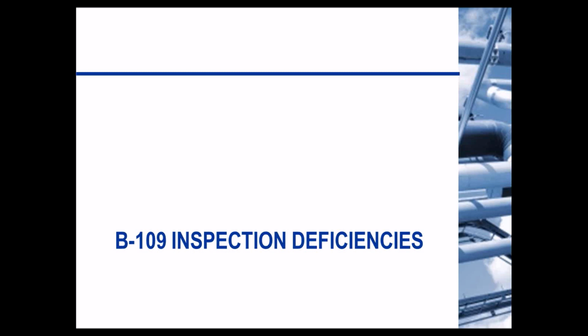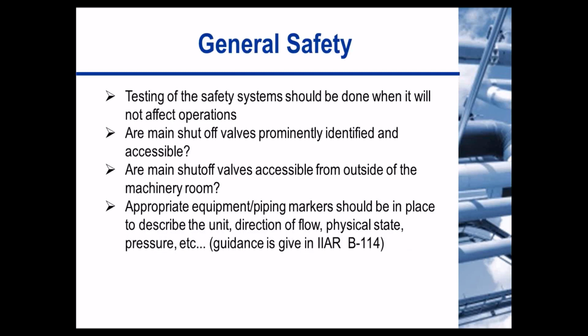So let's talk a little bit about the different inspection checklists and some deficiencies that you may see when going through and looking at these checklists. Let's talk about general safety first. There are a couple of things we should be aware of. First, any testing on systems should be done when it's not going to affect operations, right? Some of the things where you may have deficiencies are making sure that main shutoff valves are properly identified and accessible. And the keyword there is identified. Are main shutoff valves accessible from the outside of a machinery room? It seems like common sense, but it's definitely something to be aware of.